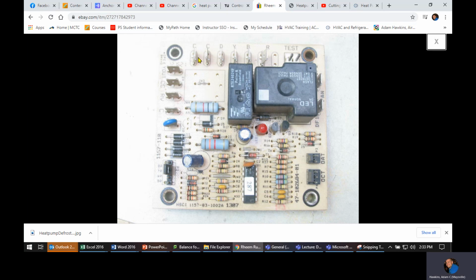And so you'll notice on this one that you have your inputs. So red, blue, yellow, D. I'm assuming that they're using that for defrost or defrost heat or something. I think on a lot of those Rheems they use D as opposed to W. So that would be your W. And then C would be your common. So you got a couple spots for common if you need an extra one. So 1, 2, 3, 4, 5.